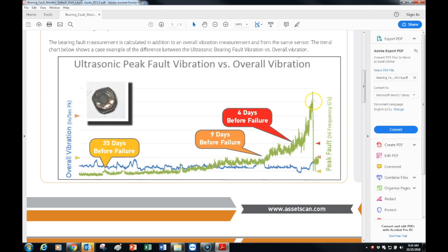So one is defining what does failure look like. This machine was not vibrating in traditional sense. It was screeching, it was smoking, it was sending out sparks, but it had not triggered any vibration issues.